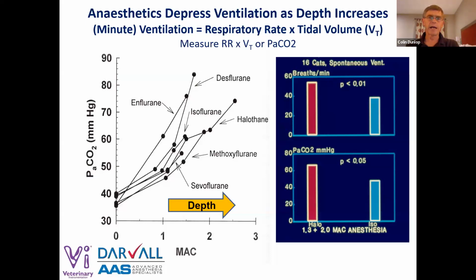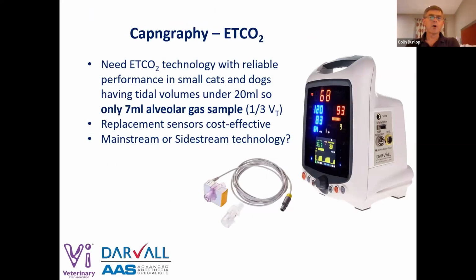So the minute ventilation in animals is around 200 mils per kilo per minute, which happens to be the flow rate, the fresh gas flow rate for a standard non-rebreathing circuit. Or we could measure the arterial blood gas, and that's certainly what we do in horses. So capnography is using some fairly simple looking equipment, a sensor, some kind of an airway adapter or a sampling tube coming into the machine where the sensor is located, to look at the gas, the inspired and expired gas, and then using infrared light to look at the light absorption to determine the CO2.